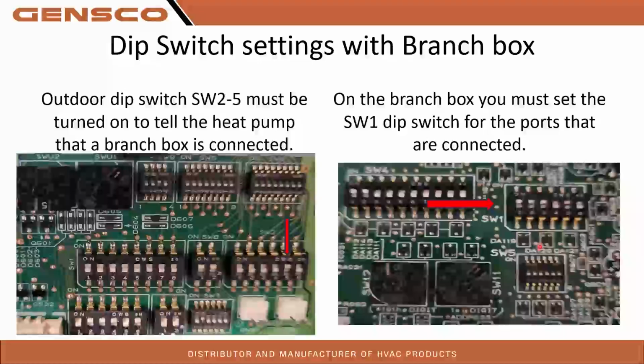So one thing to add to that, Garrett, is Mitsubishi said they would like you to use these in order. Yes. Right now, keep in mind that on a 5-port, we have E on here. E is your 1/2-inch suction. So if you do have a 1/2-inch suction, you can put it there and skip one. So other than that, if you have all 1/4, 3/8 lines, they prefer that you use them in order. Go right down the line. They don't want you to skip ports, but can you? Yes. But anyways, so yeah, making sure that you turn those on.